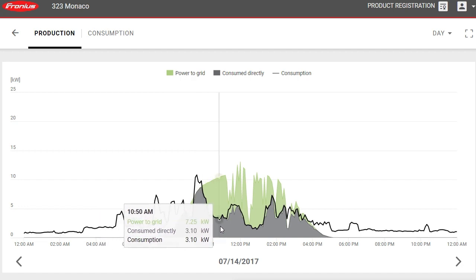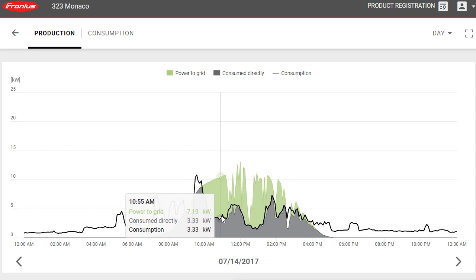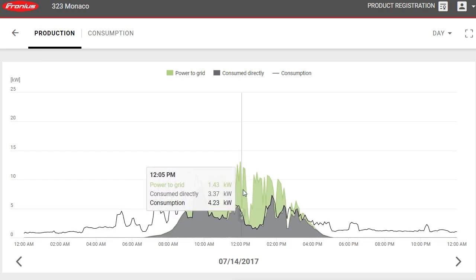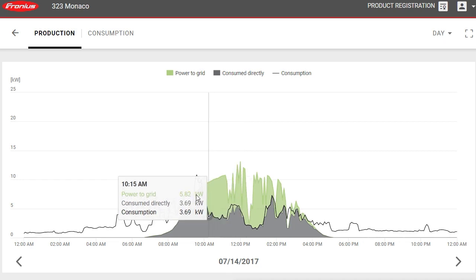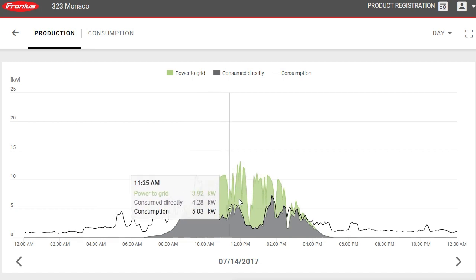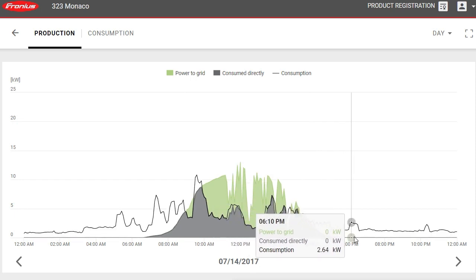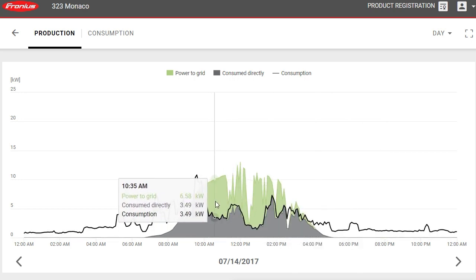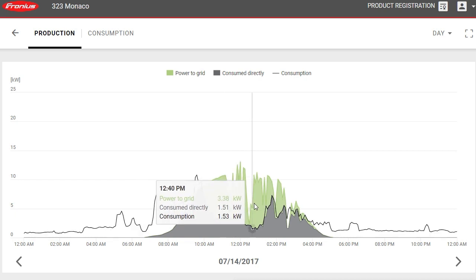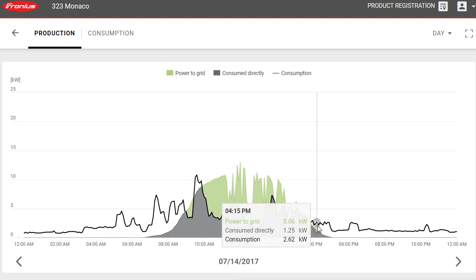The loads jump up again so the solar isn't quite covering them, then they drop off again. We can see cloud building up, causing these big jagged cuts in solar production. Still, throughout most of the day the solar has been covering the loads completely. If there was a battery, all this surplus would be going into it; and when the solar is no longer enough to cover loads, the battery would start discharging into the house.